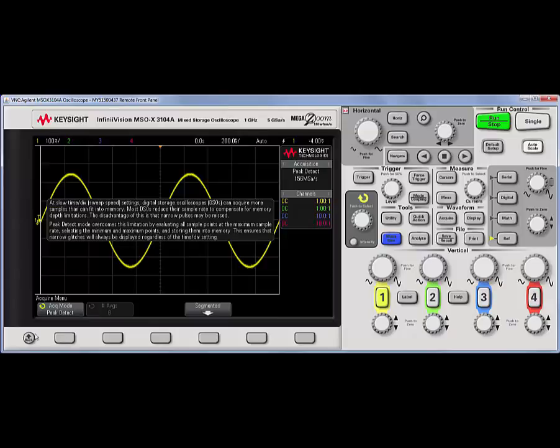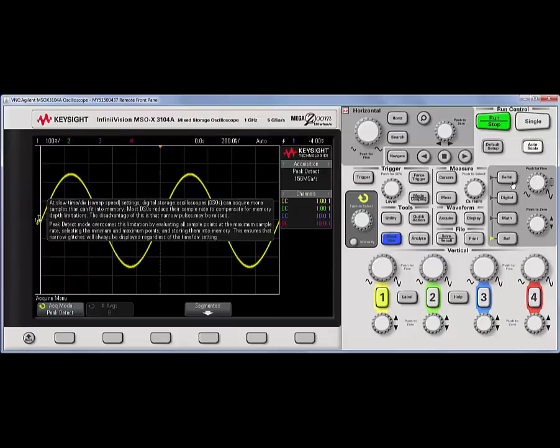Now, let's take a look at what these multiplex knobs and LEDs are for. The knobs can control the vertical scaling of the digital, math, and reference waveforms. They are not used for the serial waveform.